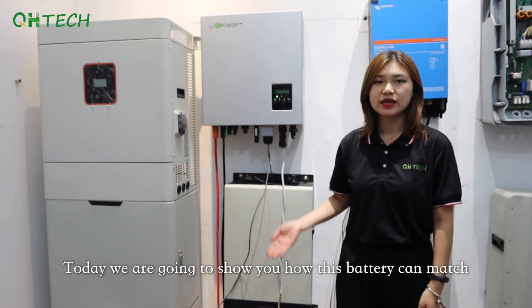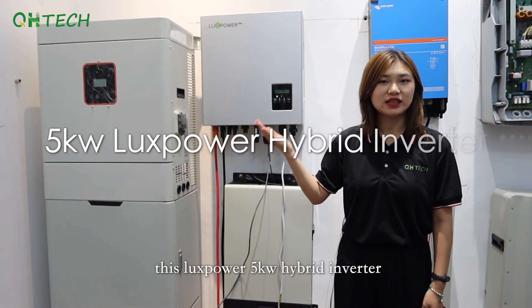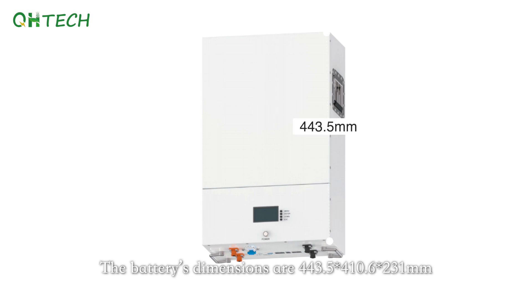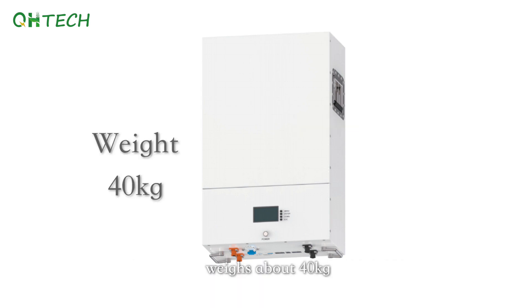Today we are going to show you how this battery can match this Luxpower 5kW hybrid inverter. The battery's dimensions are 443.5 x 410.6 x 231 millimeters, weighs about 40kg. Its charge current is 100A and discharge current is 100A. Its communication methods are RS232, RS485, and CAN. Its working temperature ranges from -20°C to 60°C. It has about 5000 cycle life and a 5-year guarantee for the battery.